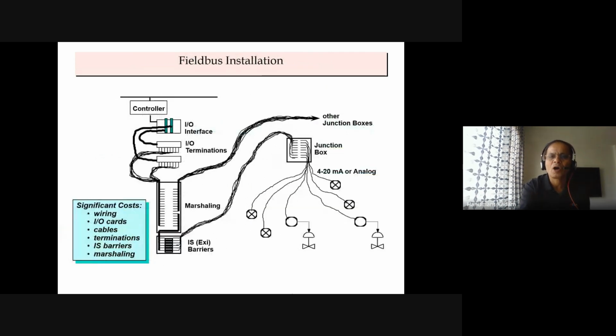If you compare, normal wiring is like this: each transmitter has two wires to the junction box, and all these device wires come to the marshalling cabinet, then this bunch of wires is terminated at IO terminations and goes to the controller like this.